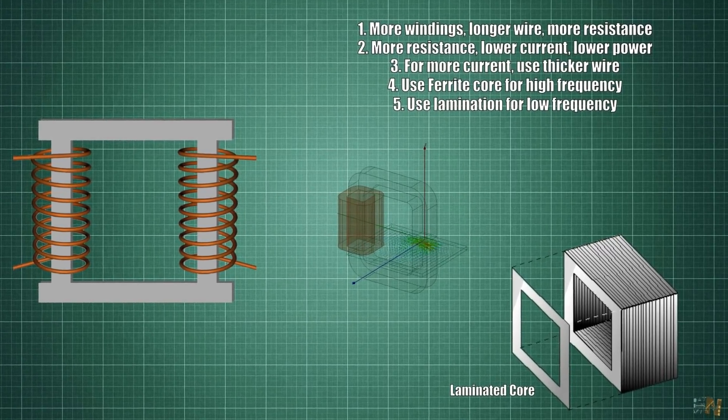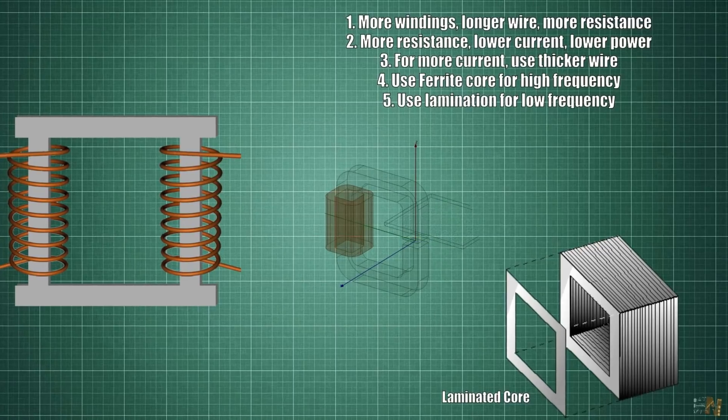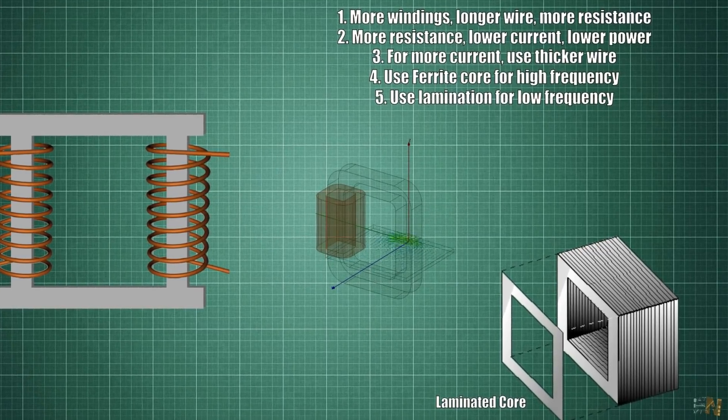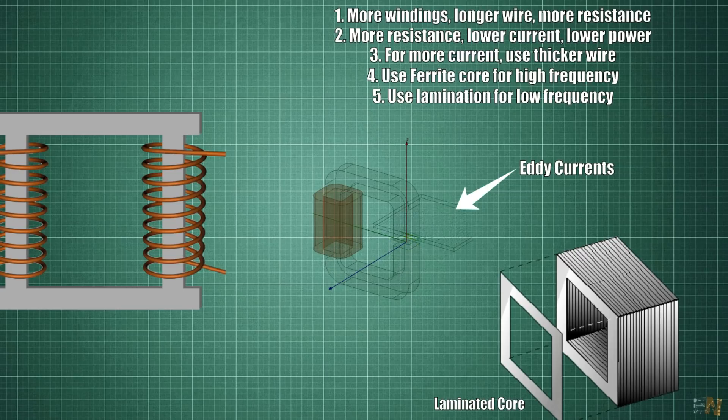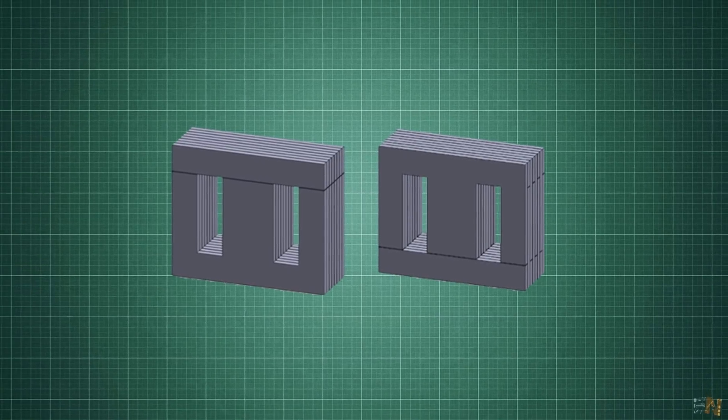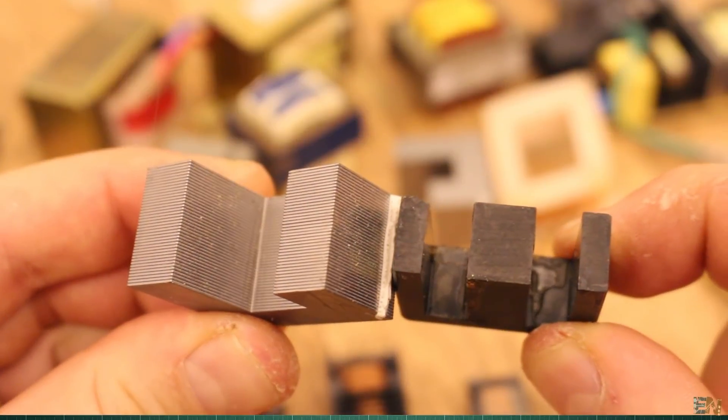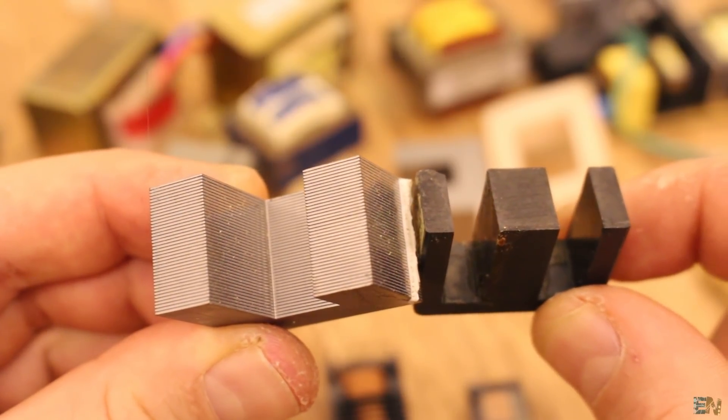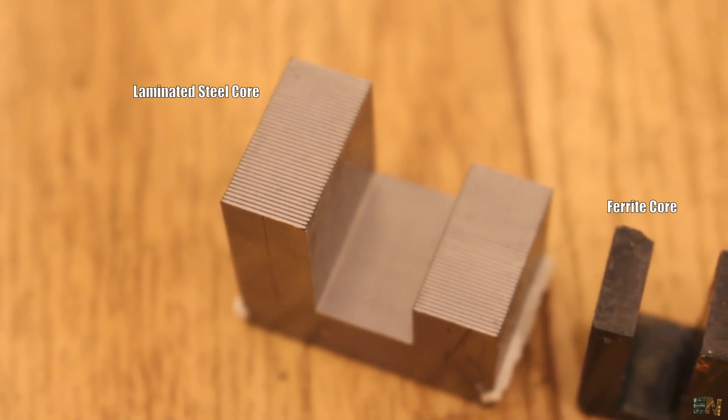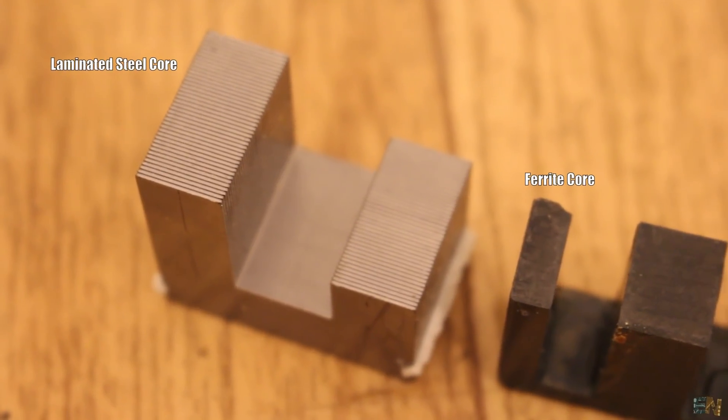With lower frequencies, core material selection is driven by the core saturation considerations. The eddy current losses are low, so steel laminations can be considered. That's why pretty much all the steel transformers are laminated to avoid eddy current problems. With higher frequencies, eddy currents can be significant, so here a ferrite core is commonly used because their high electrical resistivity minimizes the eddy current losses.